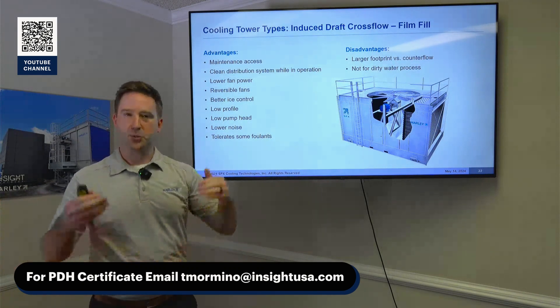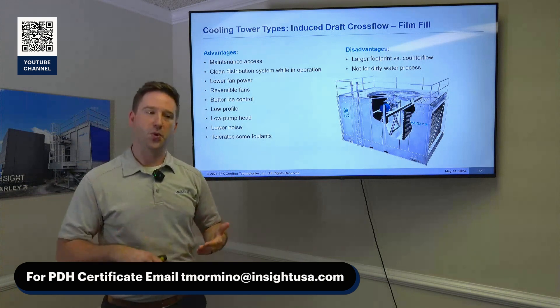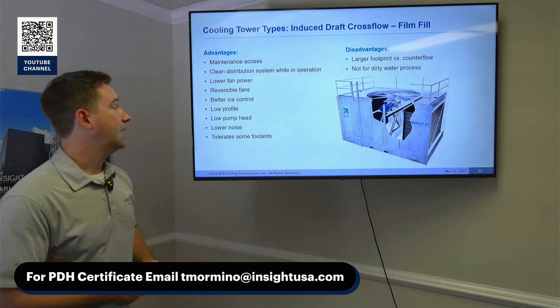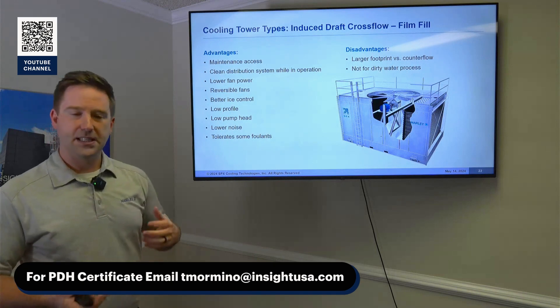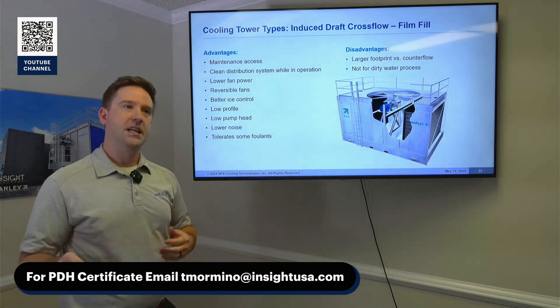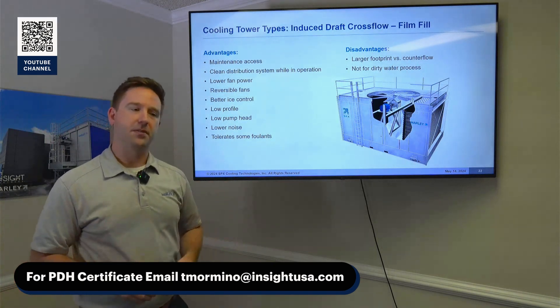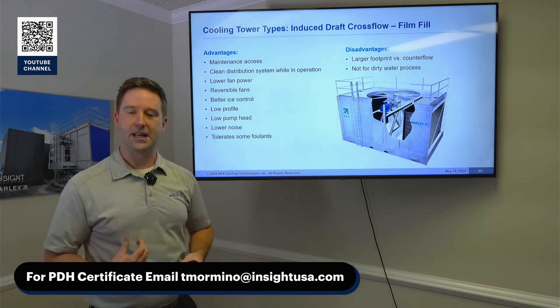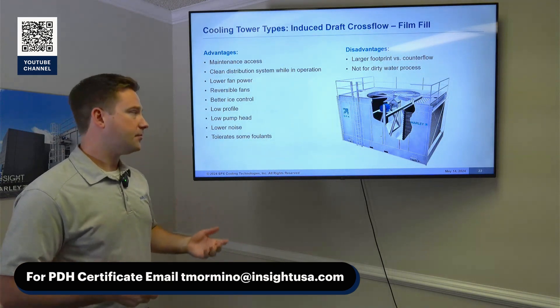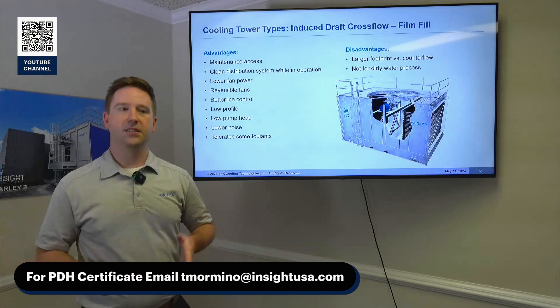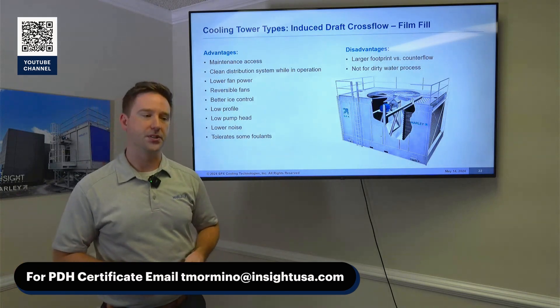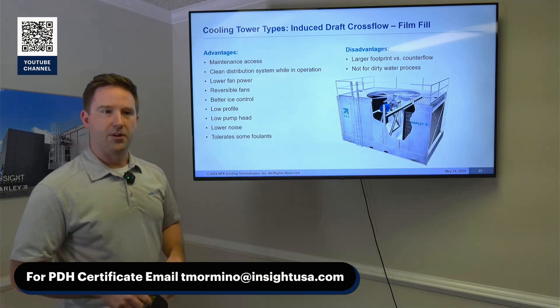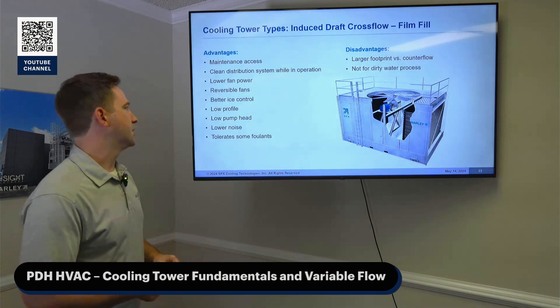Whenever you're able to reduce the flow in a controlled way, it helps maintain operation in cold weather. When I say it's a larger footprint, that's typically under 750 tons compared to a counter-flow tower. But once you get above that, the cross-flow tower will typically have a smaller footprint. Right around 750 tons is where that switches over.